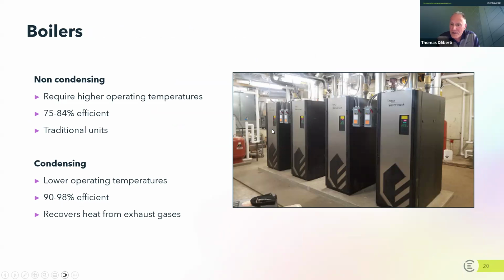The image over here is of 4 condensing boilers. And the main takeaway about boilers is we've evolved from non-condensing boilers to condensing boilers. These can be operated at lower temperatures, which means they're way more efficient during the shoulder months. And when you have four of them stacked end to end here, you can stage them on and use more and more of them during the cold time of the year. So the load that occurs in the building can be matched by how you operate your systems.